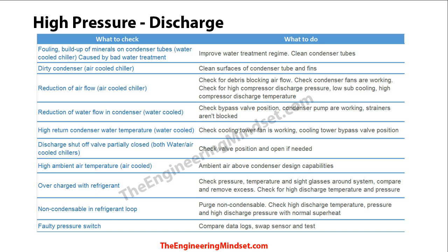Another fairly common issue is the chiller being overcharged with refrigerant — check your pressures and temperatures around the system. It could also be that a non-condensable material has entered the refrigerant loop, so check for this and purge it out if suspected. If you've checked all of the above and nothing seems wrong, it's likely a faulty pressure switch — swap it out and test it.